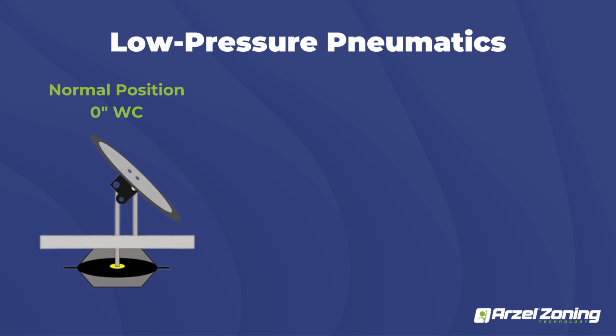So normally, the normal position on our damper with nothing going to them, so no call on the panel, they are actually open. The reason being is that when you get a call for conditioning, as your blower motor starts ramping up, your dampers will begin to close. That's so we're not starting the blower motor against closed dampers, so you don't get ductwork popping and you don't get those drawbacks. So it gives you a nice soft start on your equipment.